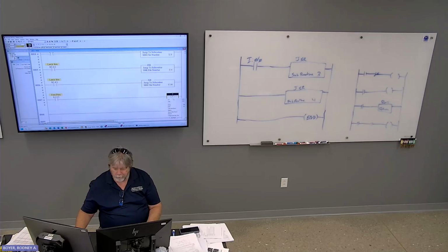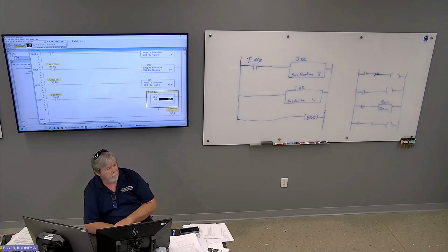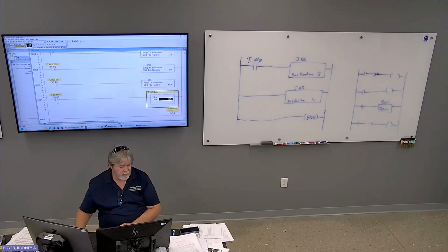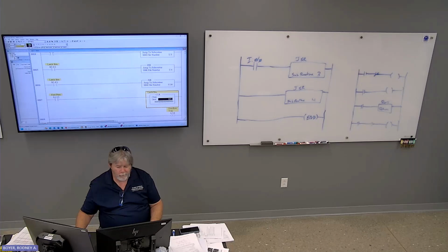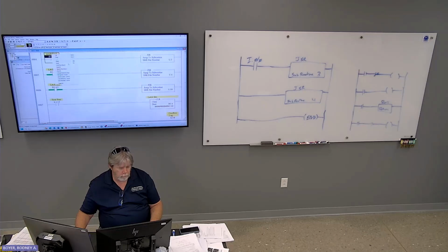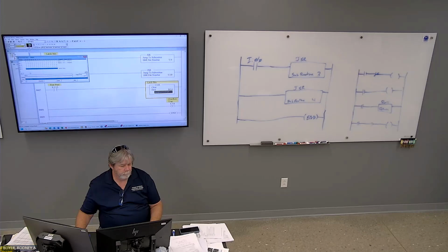Okay, let's do this. Do a clear instruction, set to the word level. So now, on first scan, it'll write all zeros into every one of those bits. On first scan, it writes a 0 to all of them. So it basically resets them all at once. Okay.